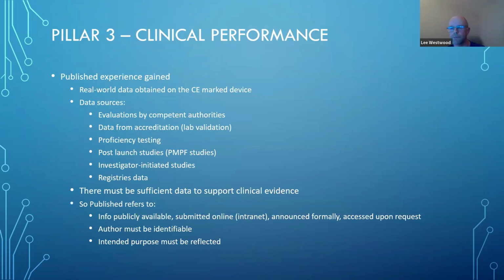The second is published experience gained. So this is real world data. Okay, so this is data that you gather on an already CE marked device. Now that is the critical point here. So if you're developing a new device from scratch for IVDR submission to get approval, you're not going to have published experience gained in regards to studies with a CE marked device or routine diagnostic testing on a CE marked device.